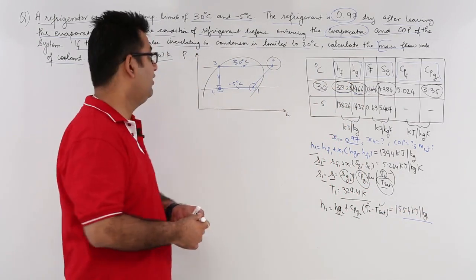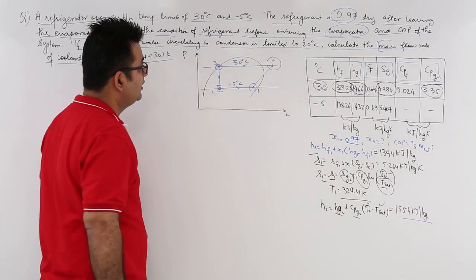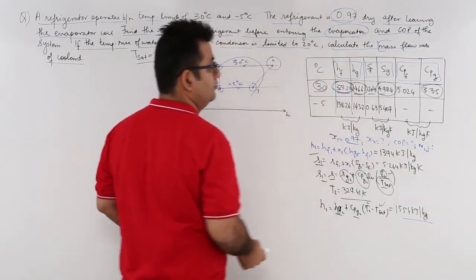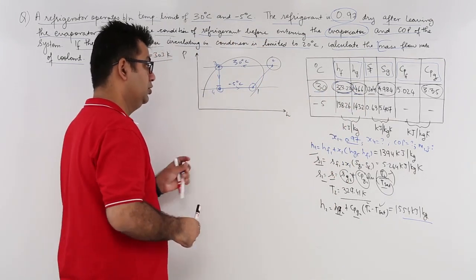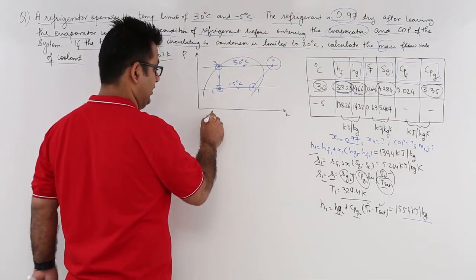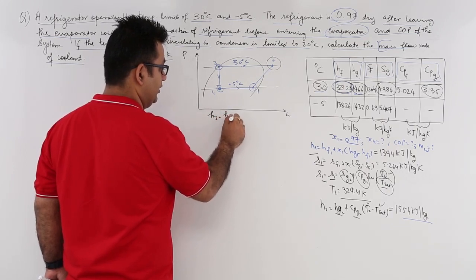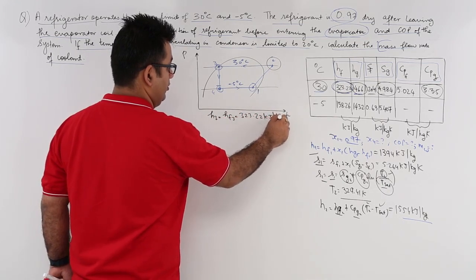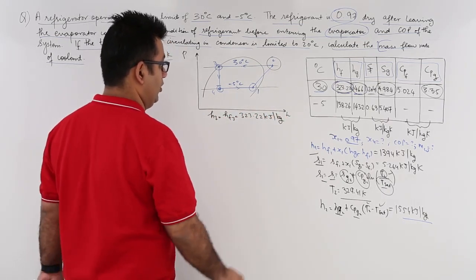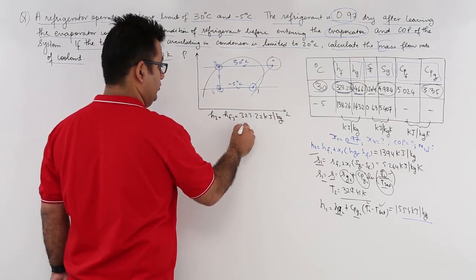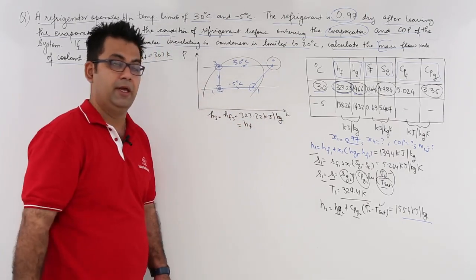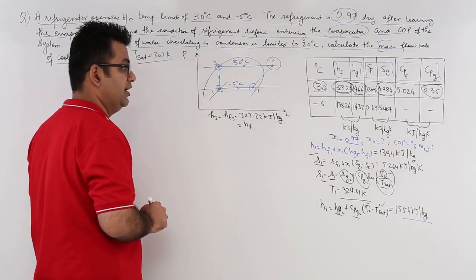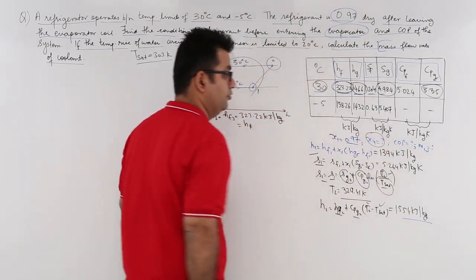After finding H2, let us find H3. At the condenser exit the refrigerant is saturated liquid at 30°C, so H3 = HF3 = 323.22 kJ/kg. Since the expansion through the throttle valve is isenthalpic, H4 = H3 = 323.22 kJ/kg.